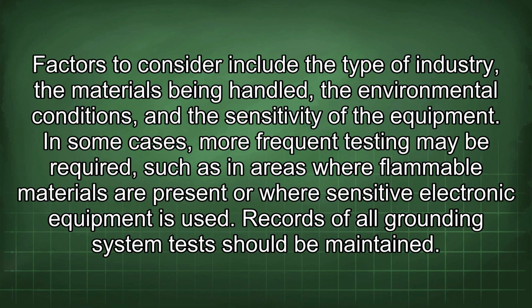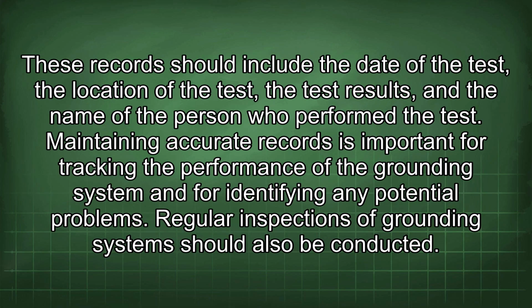In some cases, more frequent testing may be required, such as in areas where flammable materials are present or where sensitive electronic equipment is used. Records of all grounding system tests should be maintained. These records should include the date of the test, the location of the test, the test results, and the name of the person who performed the test. Maintaining accurate records is important for tracking the performance of the grounding system and for identifying any potential problems.